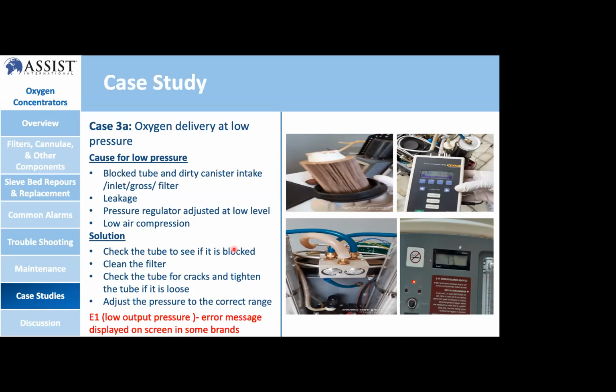The other cause is a leakage. If there is a leakage at the tube connection, in the solenoid valve, in the equalizer, or at the outlet connection, it causes low pressure delivery to the patient. So this gives an alarm or message and the machine stops running, it stops itself after a while. The other cause is the pressure regulator being adjusted at a low level. That means if the pressure regulator is adjusted at a low level, it delivers low pressure to the patient as well.